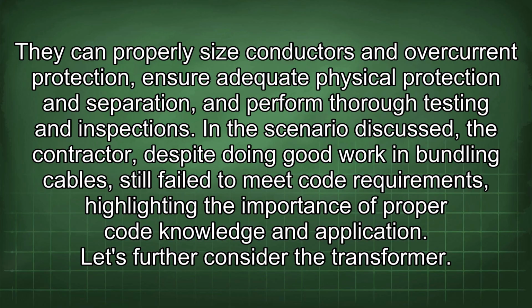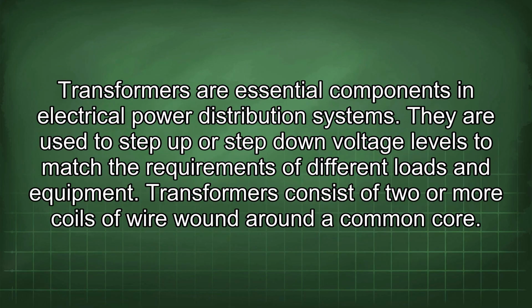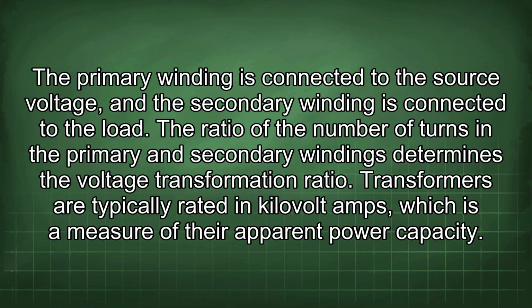Let's further consider the transformer. Transformers are essential components in electrical power distribution systems. They are used to step up or step down voltage levels to match the requirements of different loads and equipment. Transformers consist of 2 or more coils of wire wound around a common core. The primary winding is connected to the source voltage, and the secondary winding is connected to the load. The ratio of the number of turns in the primary and secondary windings determines the voltage transformation ratio.